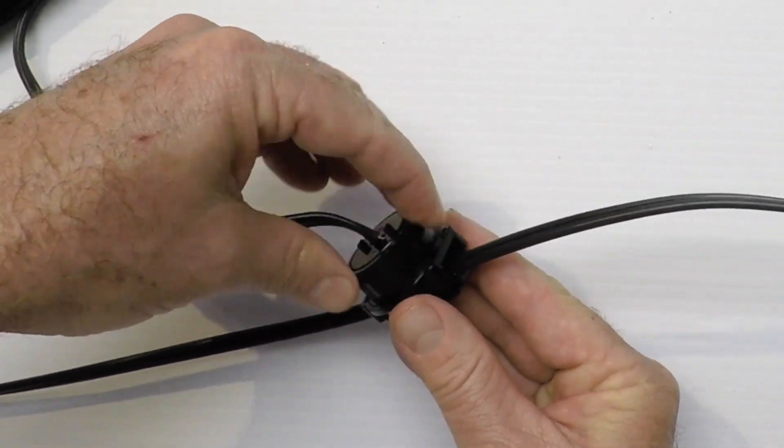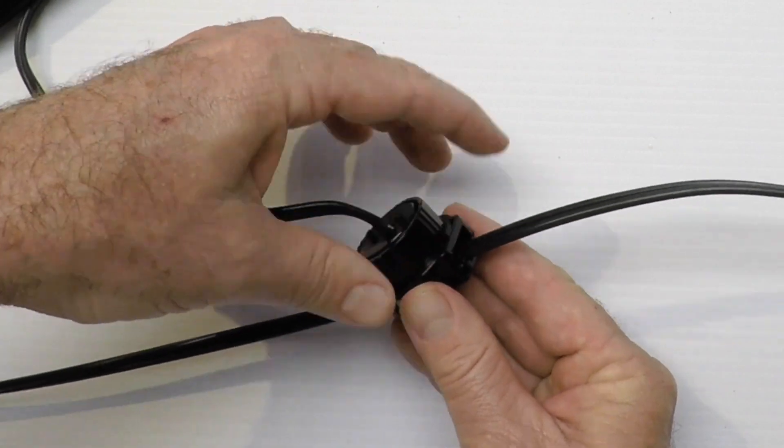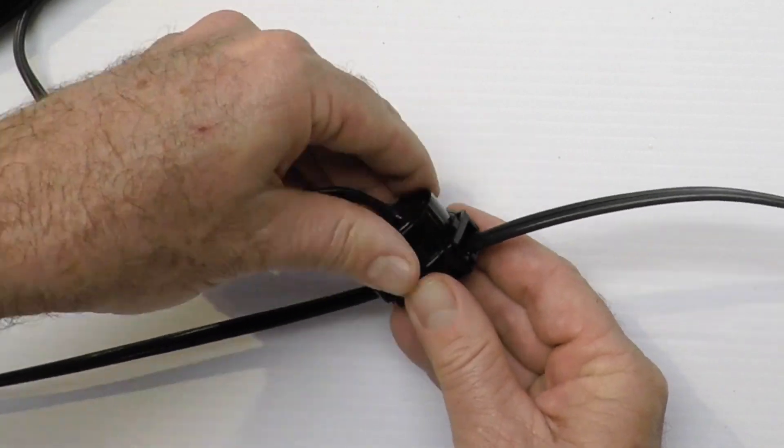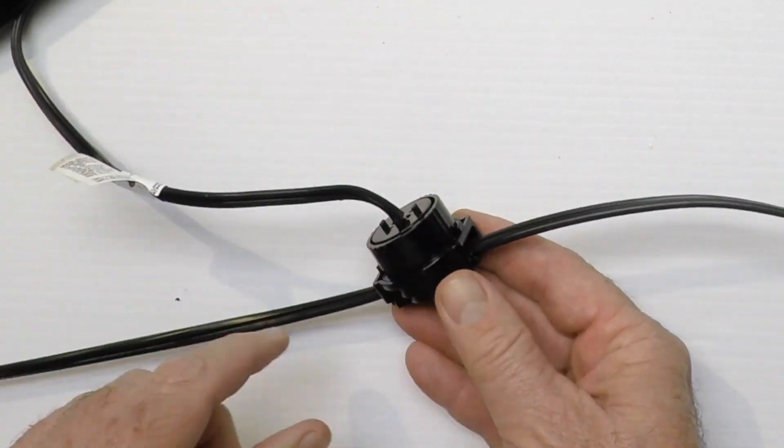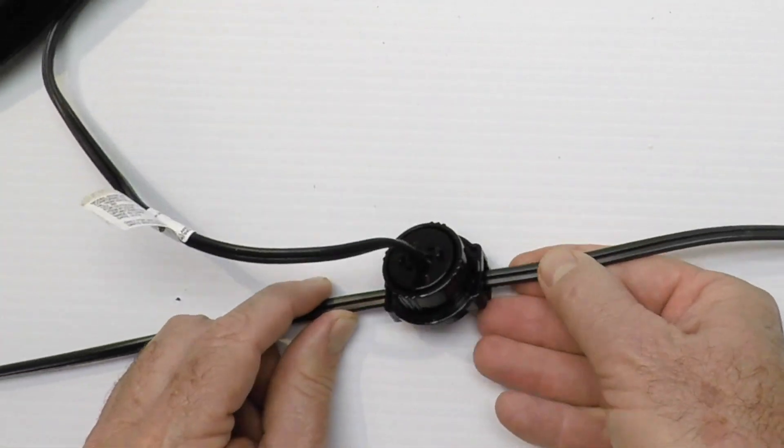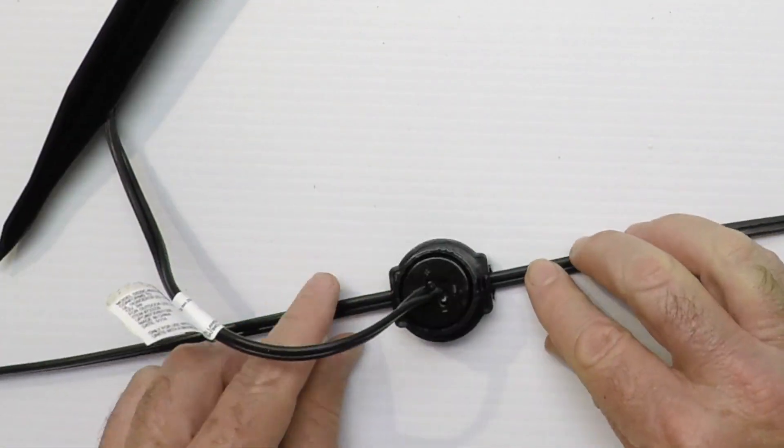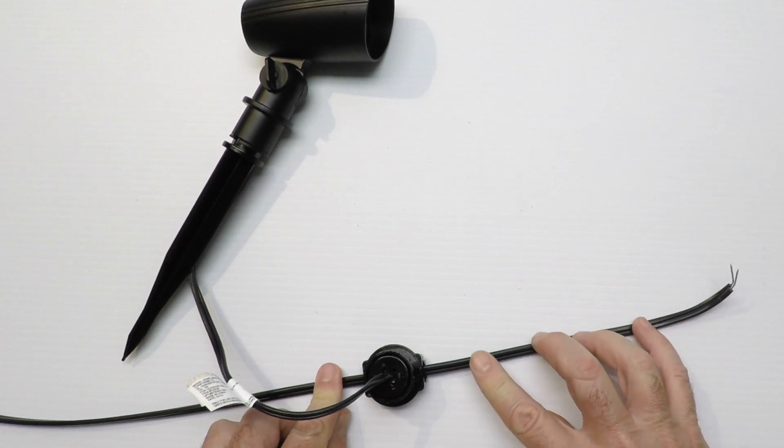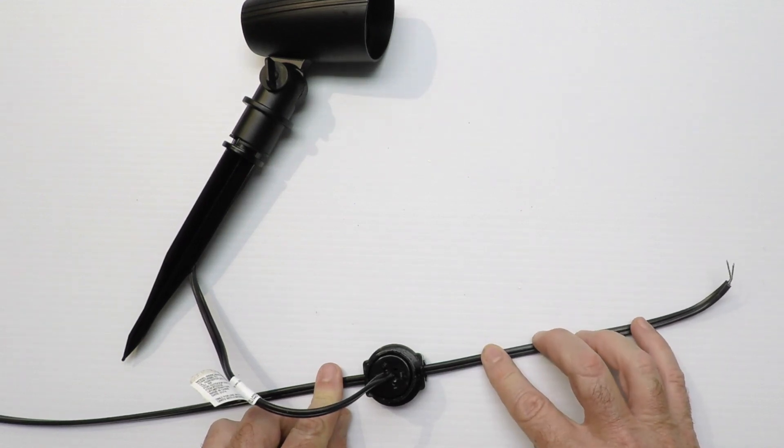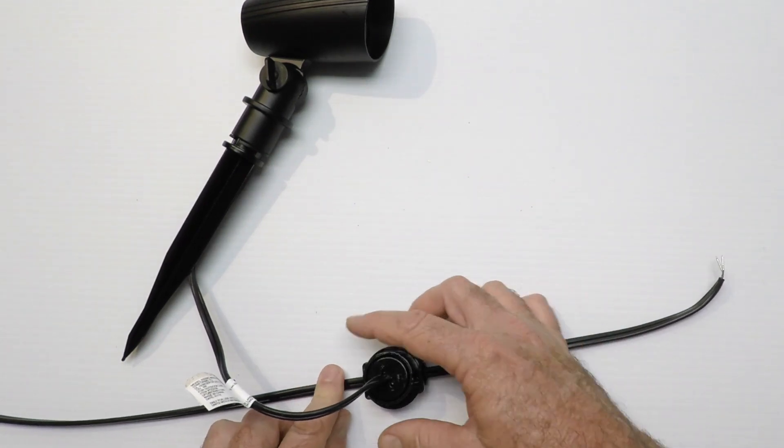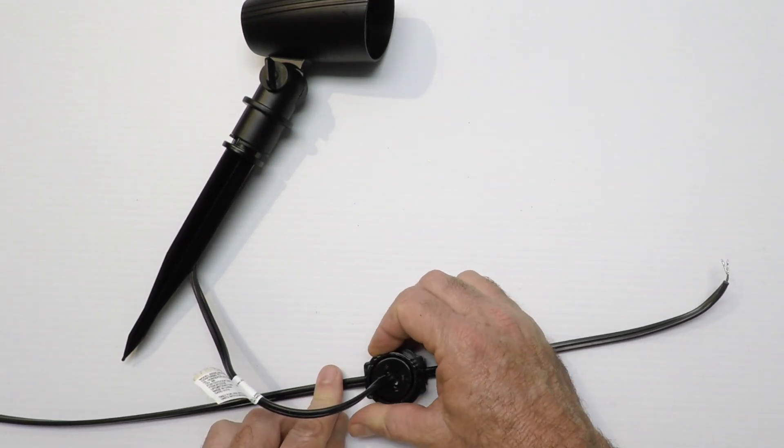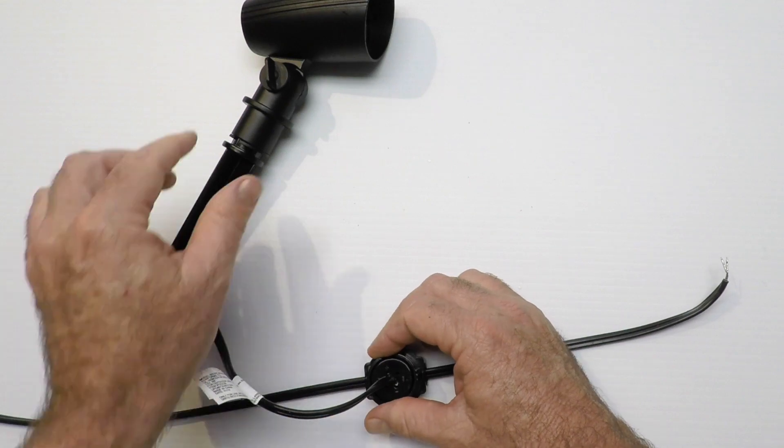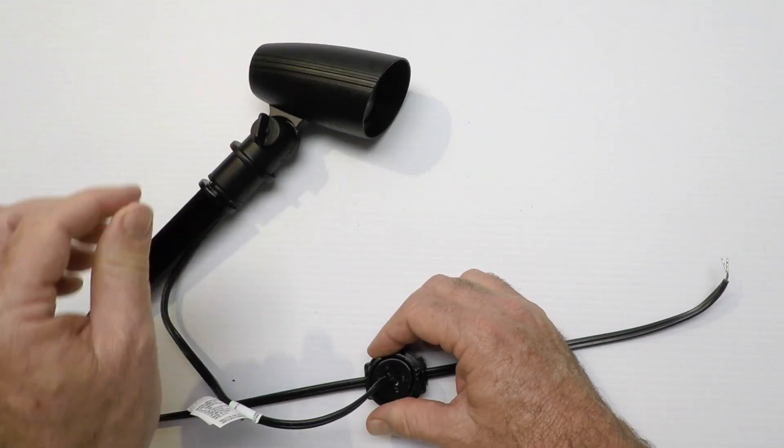When you do this, I don't want you to use tools. I want you to do it by hand. Don't get a wrench and crank this thing down. You don't need to. Now when I do this, I usually have this wire energized. Going back to the transformer, I put my transformer on test. That way when I know I got a connection, the light will come on.